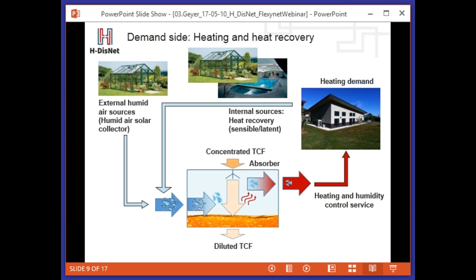At the same time, we can do heat recovery and also latent heat recovery, which means that we recover the energy that is captured in the humidity of the air that usually would go out. So usually if you have a swimming pool, it's a good example, you have to ventilate the room in the swimming pool to remove humidity. What you can do with thermochemical absorption is to remove the water from the air above the swimming pool, and that allows you to dramatically reduce the ventilation and with that the energy losses. So it's heating and heat recovery which can be provided by thermochemical absorption.